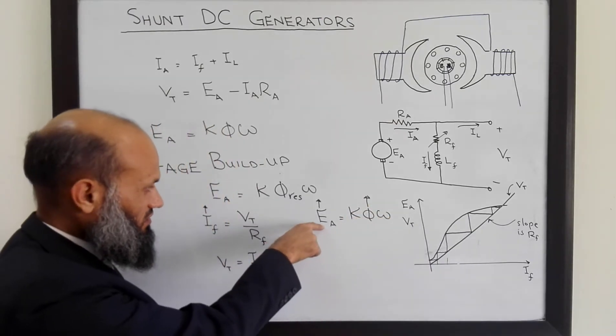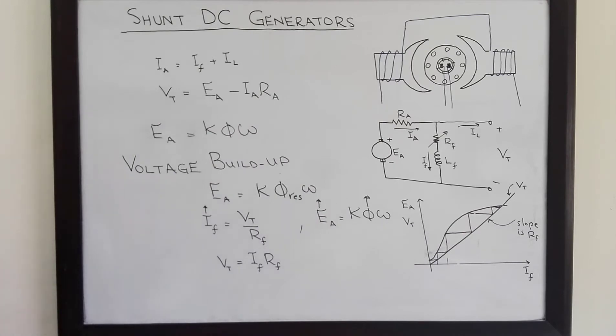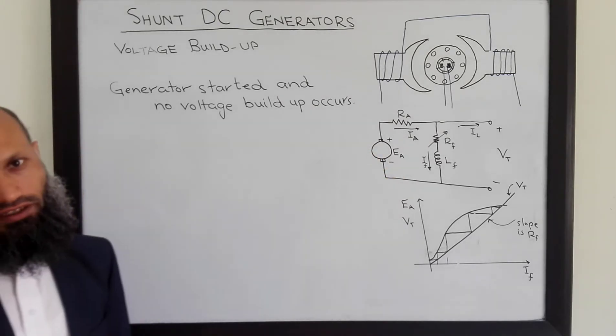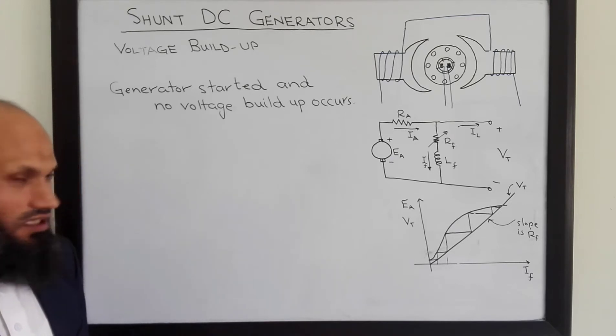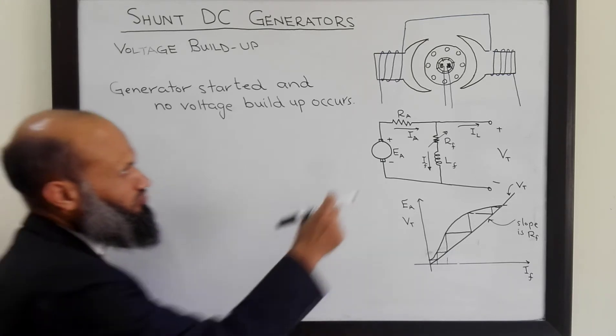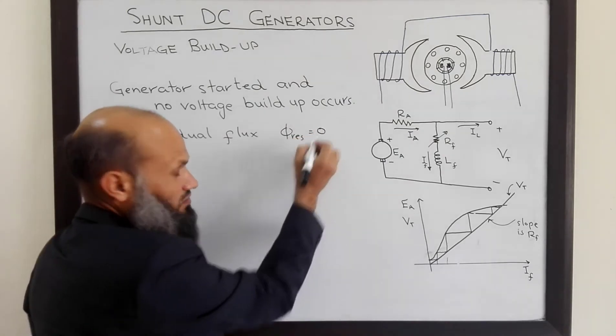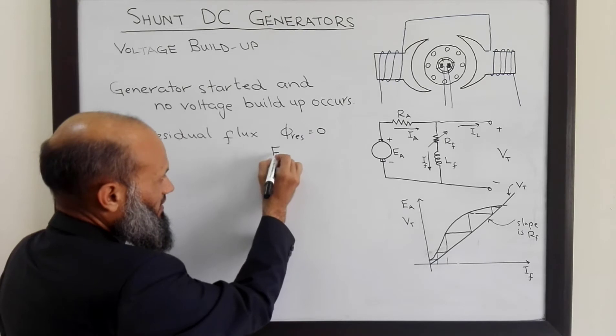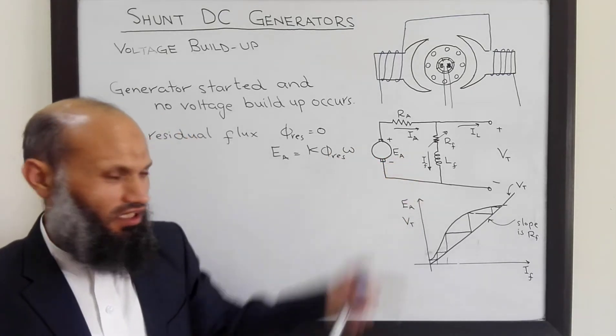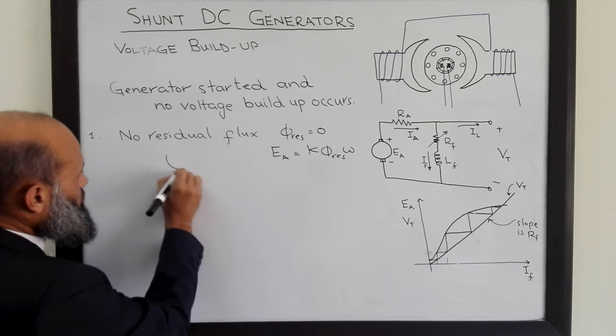Sometimes when we start the generator — that is, when we start rotating the rotor — no voltage buildup occurs. The first possible reason is that there may be no residual flux in the poles of the generator (φ_residual = 0). In that case, there is no voltage, no current, and hence no voltage buildup can occur.